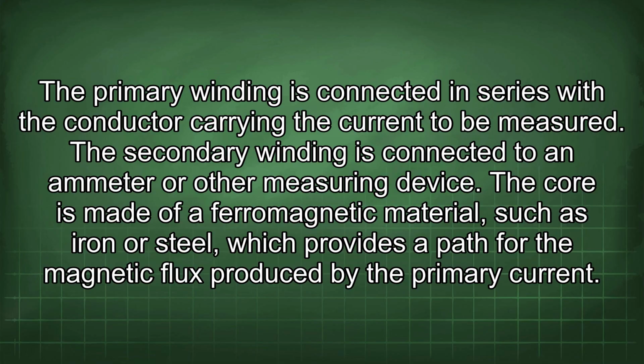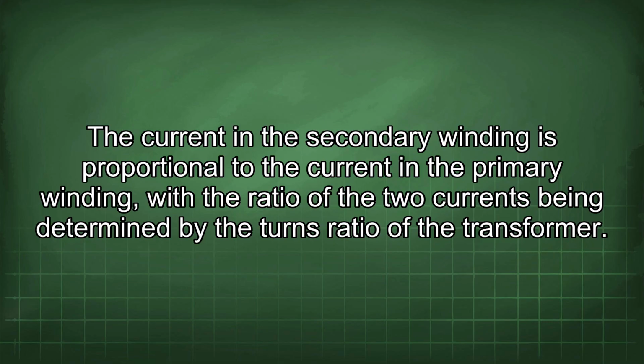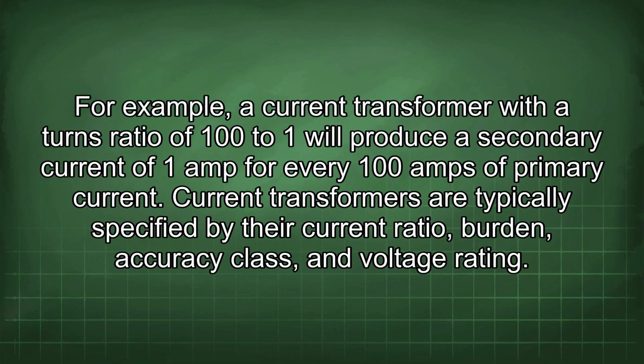The core is made of a ferromagnetic material such as iron or steel, which provides a path for the magnetic flux produced by the primary current. The current in the secondary winding is proportional to the current in the primary winding, with the ratio of the two currents being determined by the turns ratio of the transformer. For example, a current transformer with a turns ratio of 100:1 will produce a secondary current of 1 amp for every 100 amps of primary current.